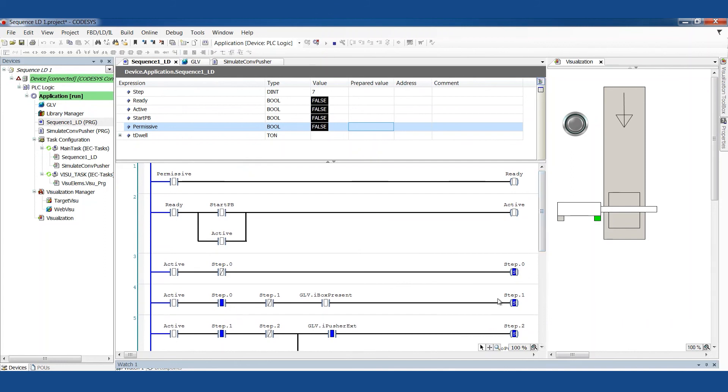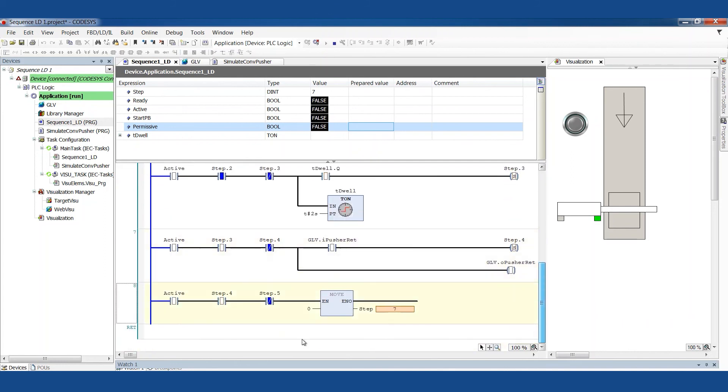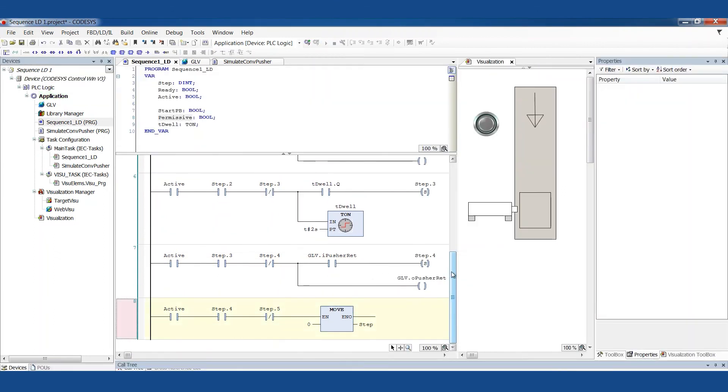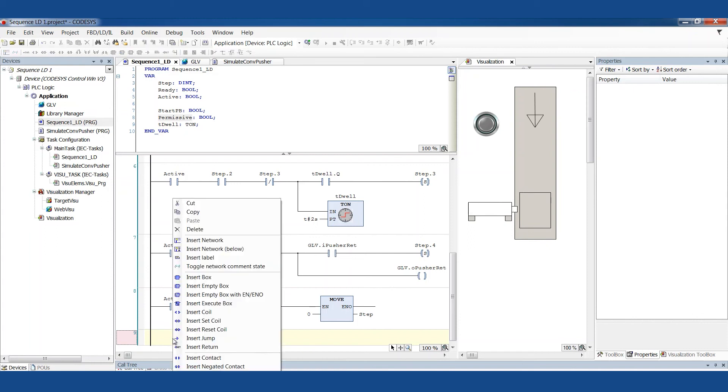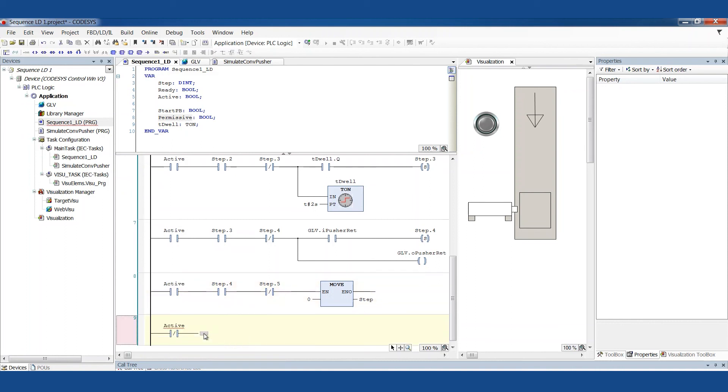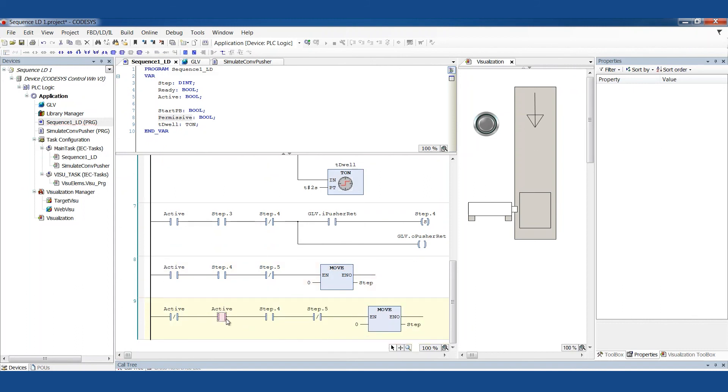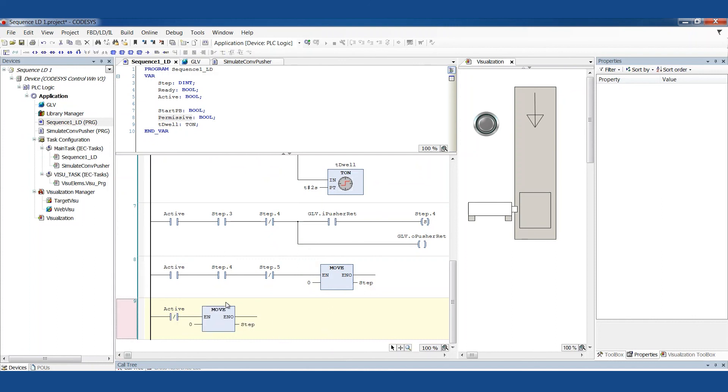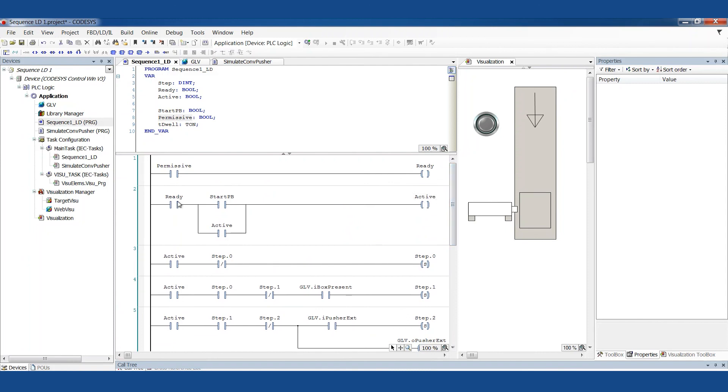So if I did want this to clear, then I would be watching somewhere. I would make another rung that said, if not active, then move zero into step. And that's just another way to catch that situation because we'll stop being active if we're not ready. And we're not ready if the permissives aren't true.